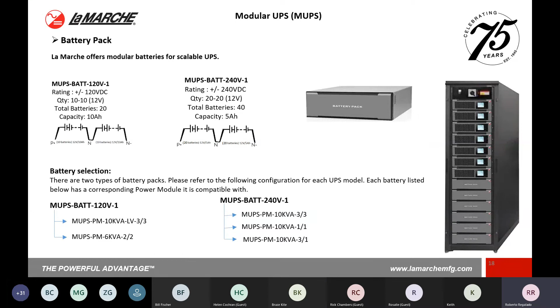The battery packs we have aren't interchangeable for any power module you want; they're designated for a certain power module. The 120 volt MUPS battery is only designated for these power modules, while the 240 volt, the higher voltage, is dedicated for the higher voltage power modules shown here. That's something to pay close attention to when configuring batteries for the MUPS.